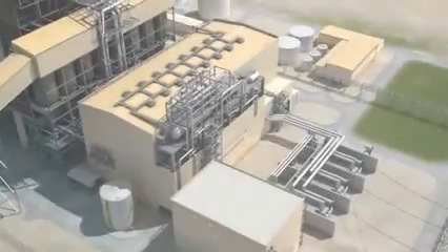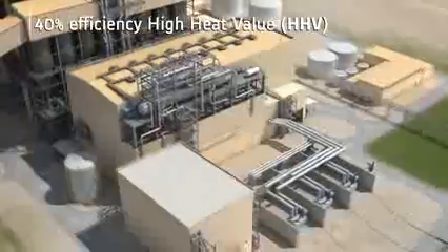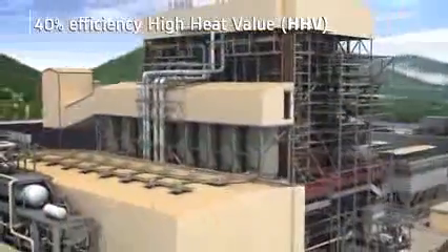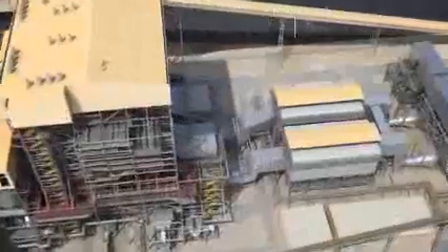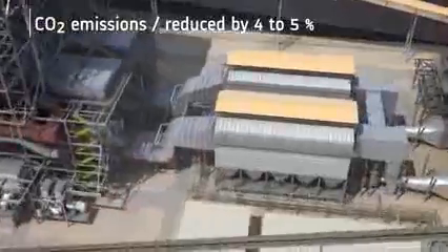When you move from subcritical conditions, with low steam parameters, to USC conditions, ultra supercritical conditions like what we have in Manjung, you increase the efficiency by 3 to 4 percentage points. What does it mean in terms of CO2 emissions? They are reduced by 4 to 5%, so really a tremendous progress in this area.